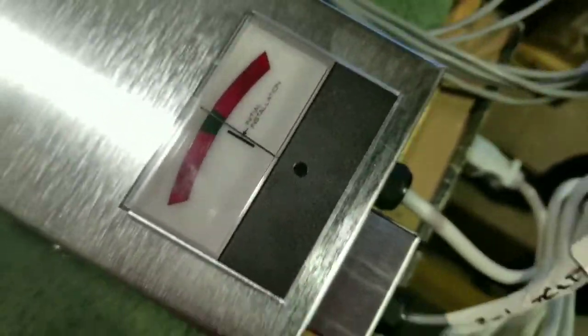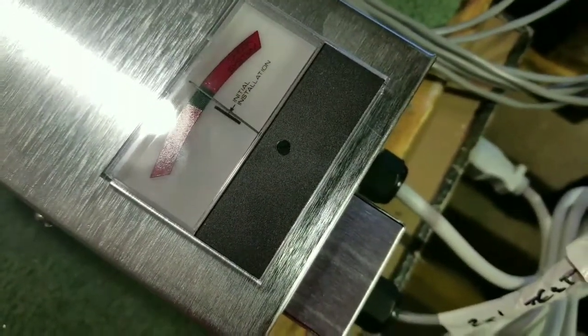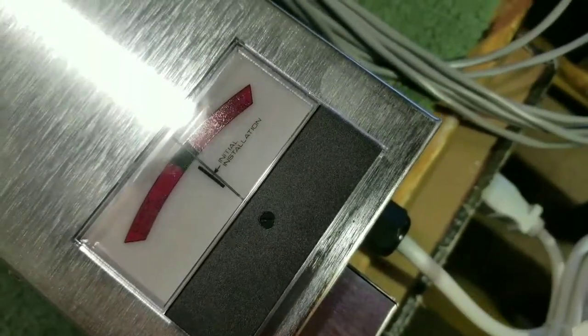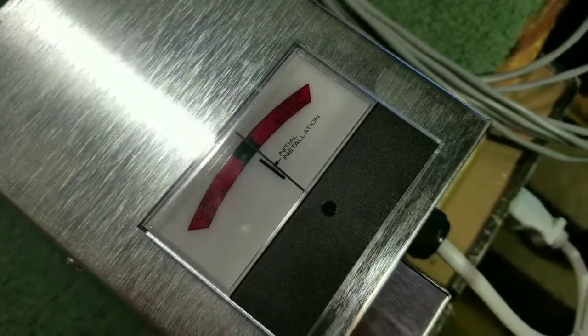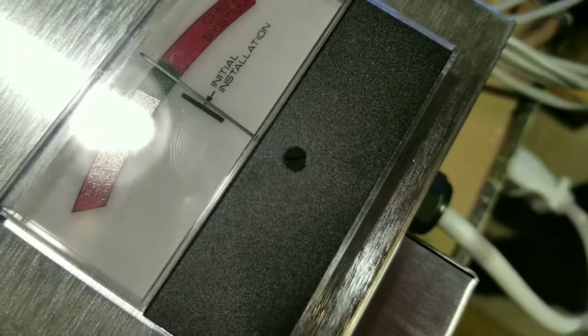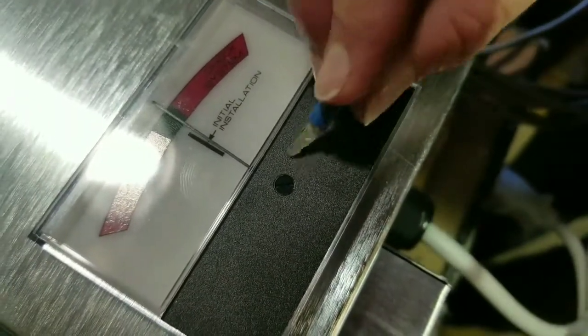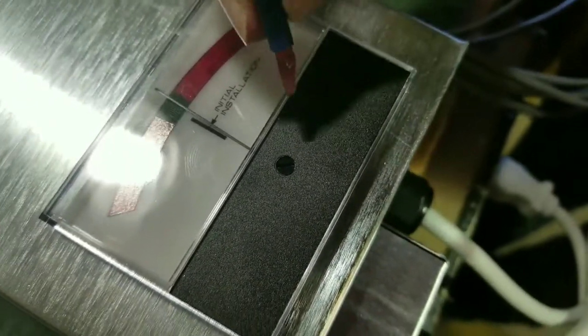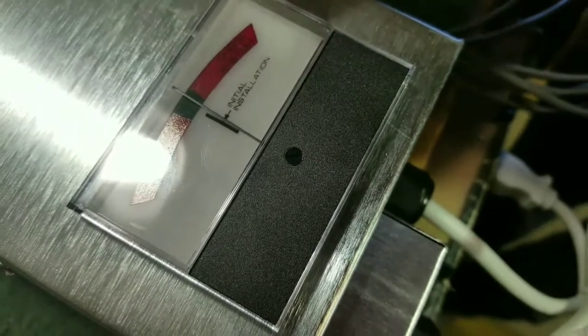And you can see here that it's been calibrated here at our warehouse, but you may need to, depending on airflow, adjust that needle. So at the fulcrum of the needle, there is a small place for a flathead screwdriver. You'll need to use a non-magnetic screwdriver to adjust the needle.